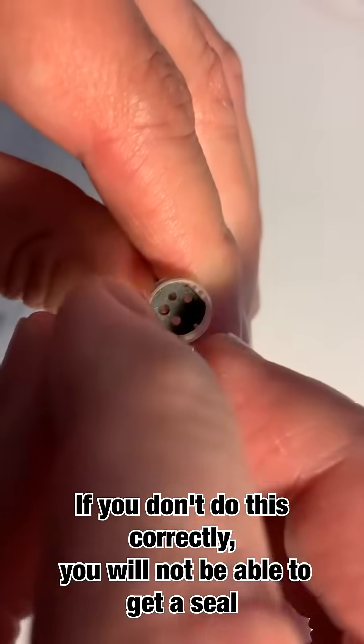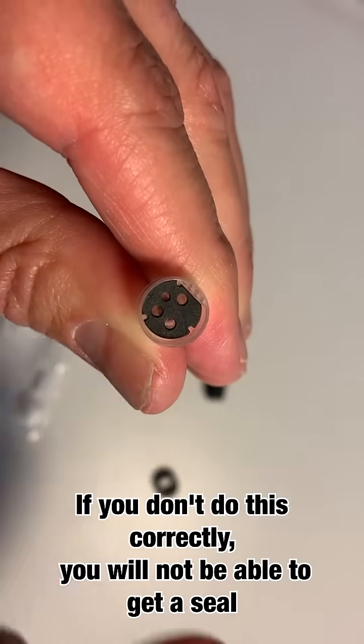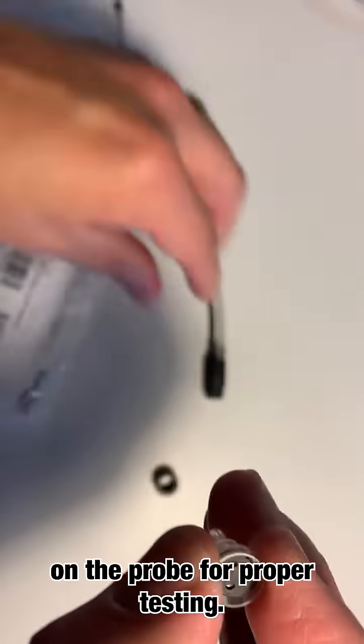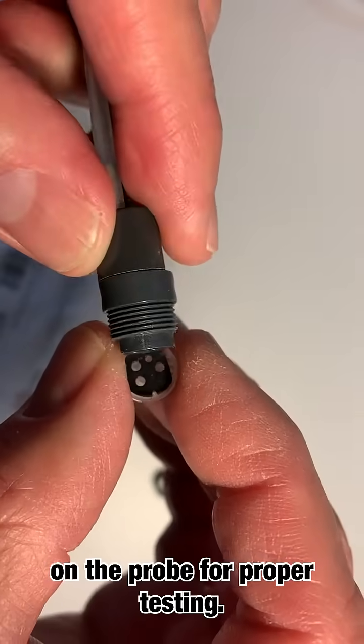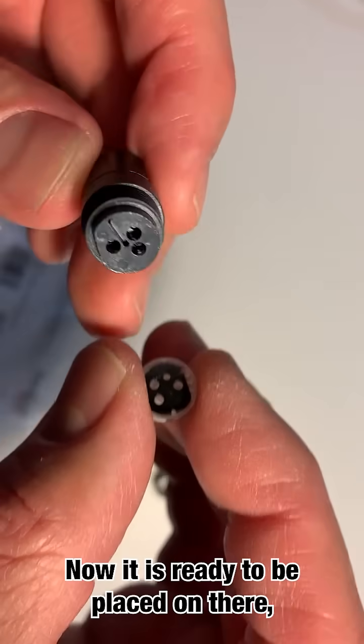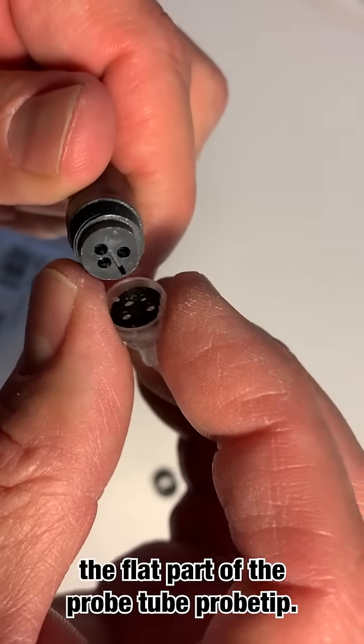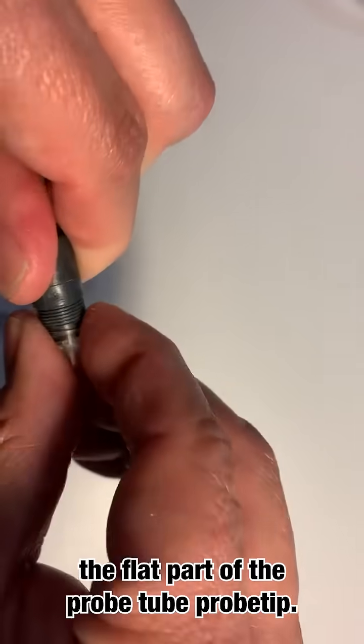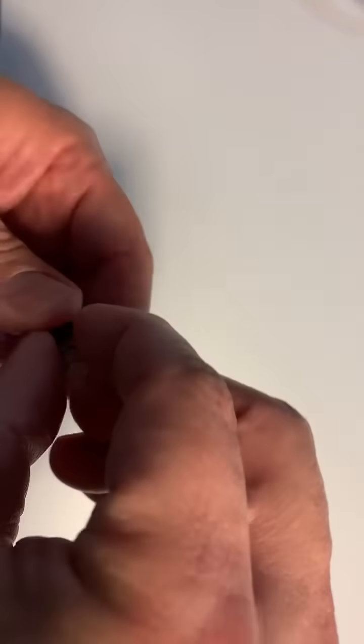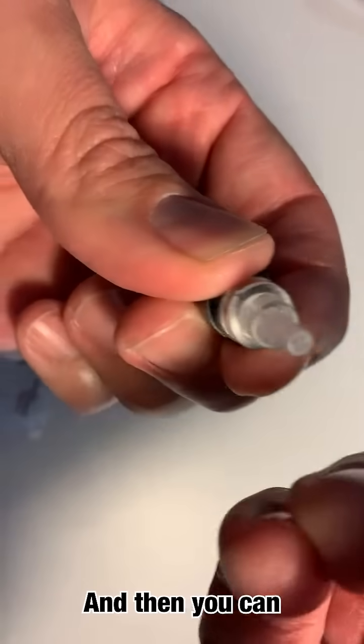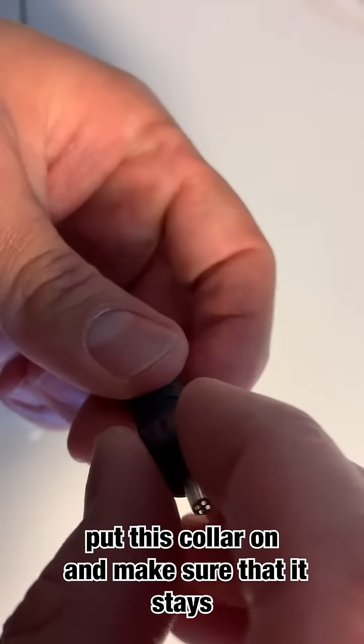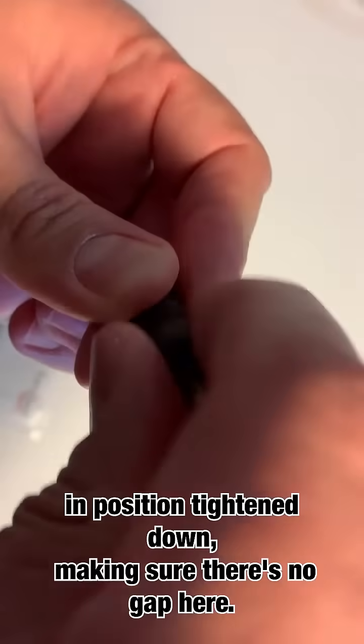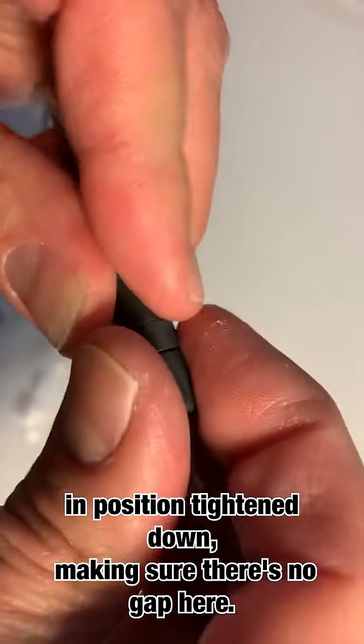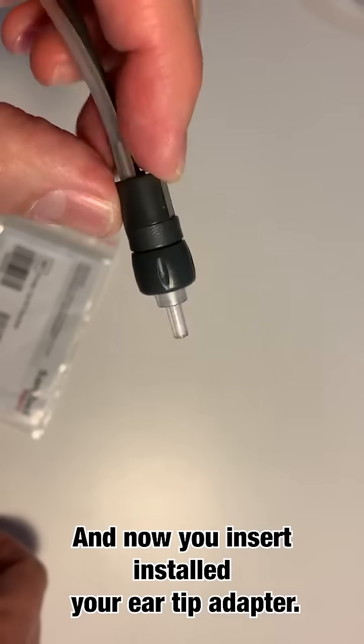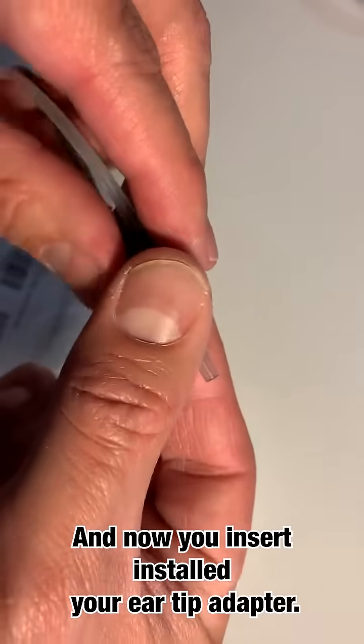If you don't do this correctly, you will not be able to get a seal on the probe for proper testing. Now it is ready to be placed on there, the flat part of the probe tip. And then you can put this collar on and make sure that it stays in position, tighten down, making sure there's no gap here. And now you've installed your ear tip adapter.